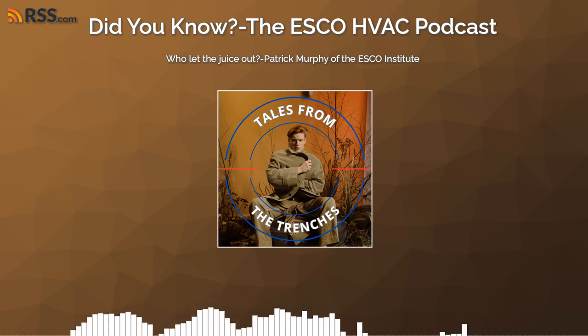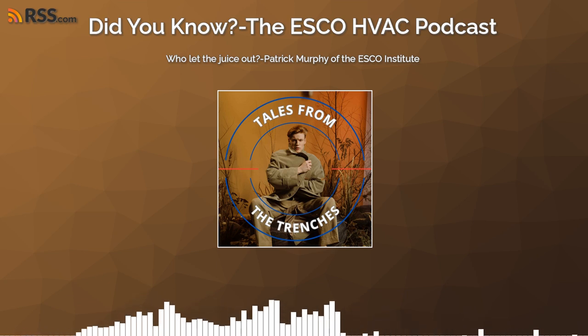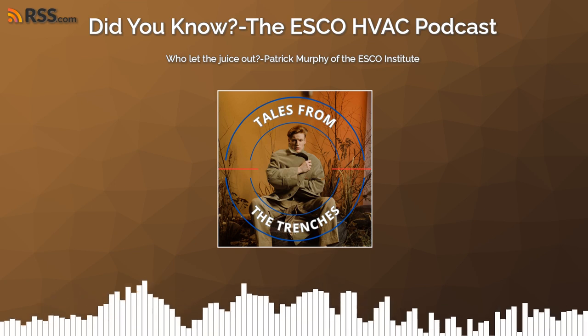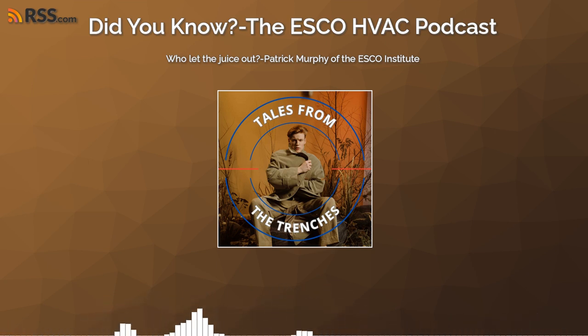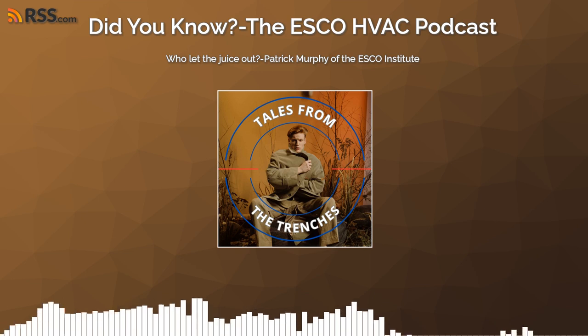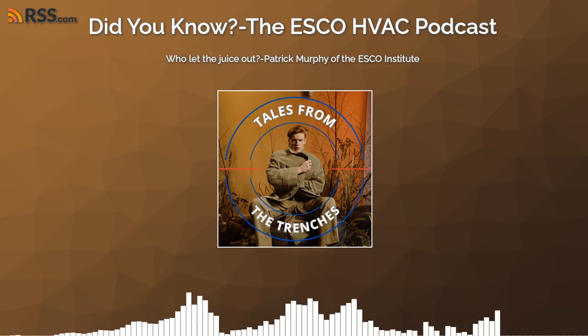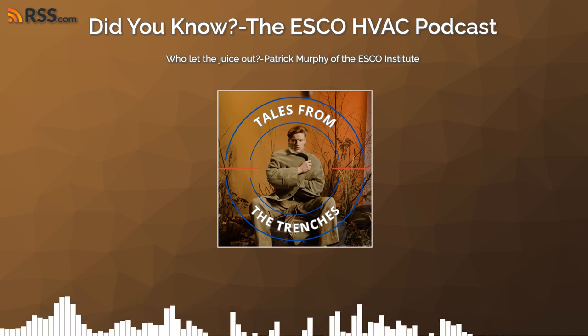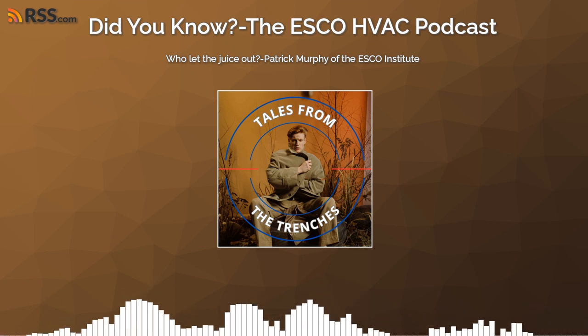The trench was covered over with a wooden floor, because at that time they put wooden floors in meat rooms. We could not find the leak in the cases or in the machine room. One of the guys said, 'I'm going to find this leak,' and he attached his leak detector to a 50-foot length of quarter-inch copper tubing. The trench to the meat room was right off the machine room, so we ran that tubing in. At about 25 to 30 feet in, we picked up a leak. The carpenters were still on the job site, so we made them tear the floor up. The sleepers were 16 inches apart, and the nail that was shot into the suction line from a Hilti gun was dead center between the two of them — just one of those leaks that was almost impossible to find.